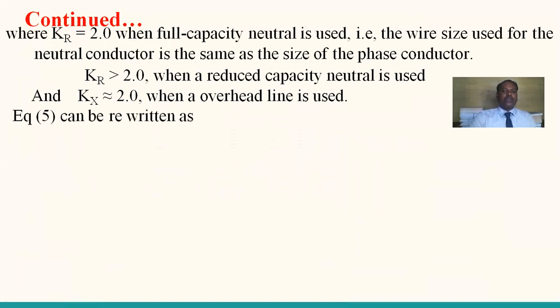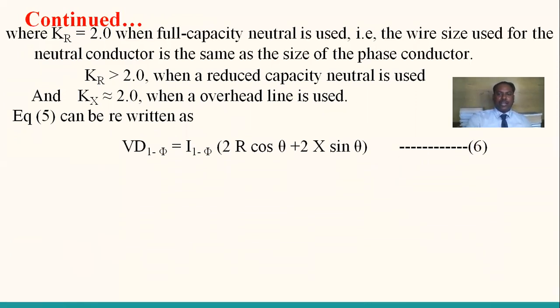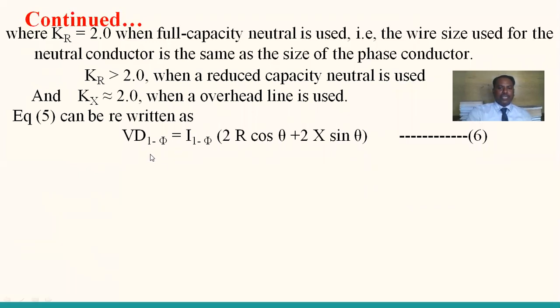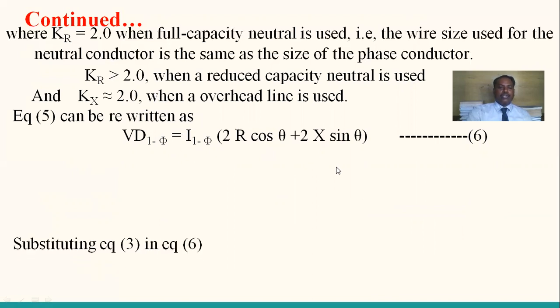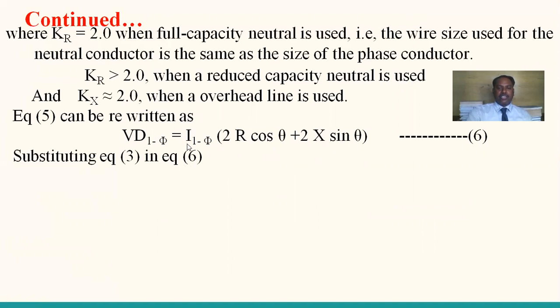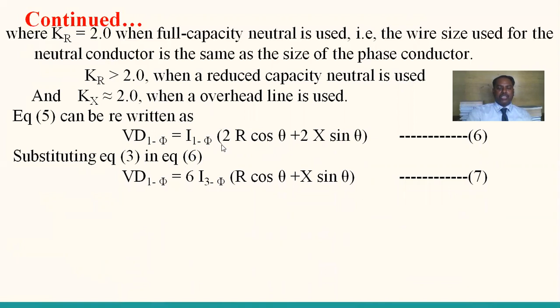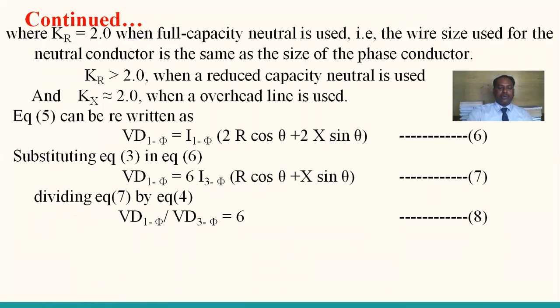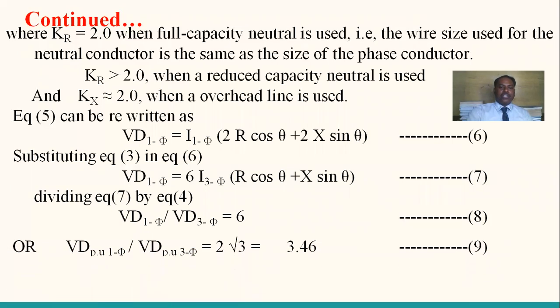Substituting these Kr and Kx values in equation 5, it can be simplified as: the voltage drop of a single phase system is equal to the single phase current into Kr equal to 2, R cos theta plus Kx equal to 2, X sin theta. Substituting equation 3 in equation 6, where equation 3 is I single phase equal to 3 times I three phase, take the 2 as common and substitute it in equation 6. The voltage drop of a single phase system is equal to 6 times the three-phase current multiplied by R cos theta plus X sin theta. Dividing equation 7 by equation 4, where equation 7 is the voltage drop of a single phase system and equation 4 is the voltage drop of a three-phase system, all the terms cancel. So the voltage drop of the single phase system divided by the voltage drop of the three-phase system is equal to 6.